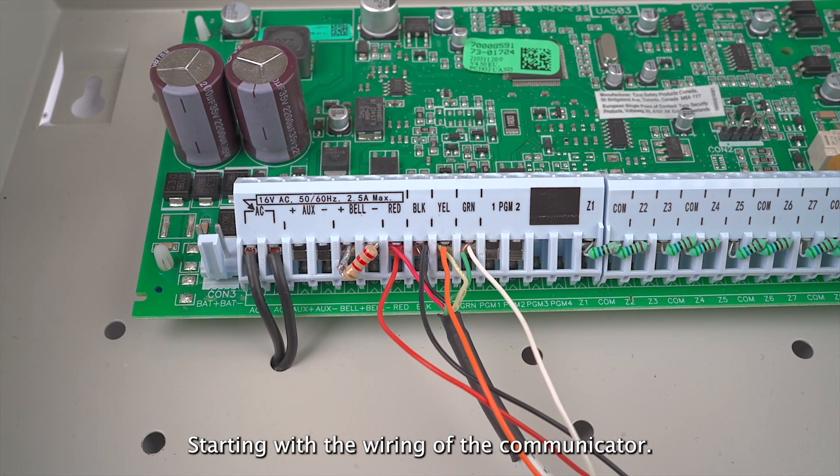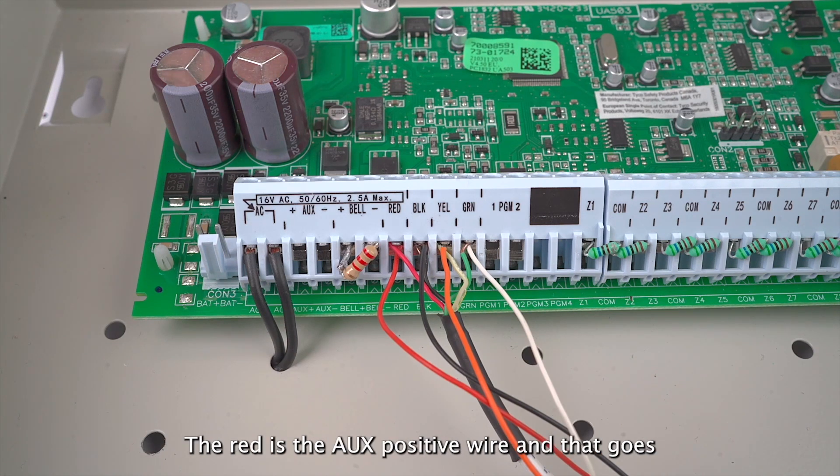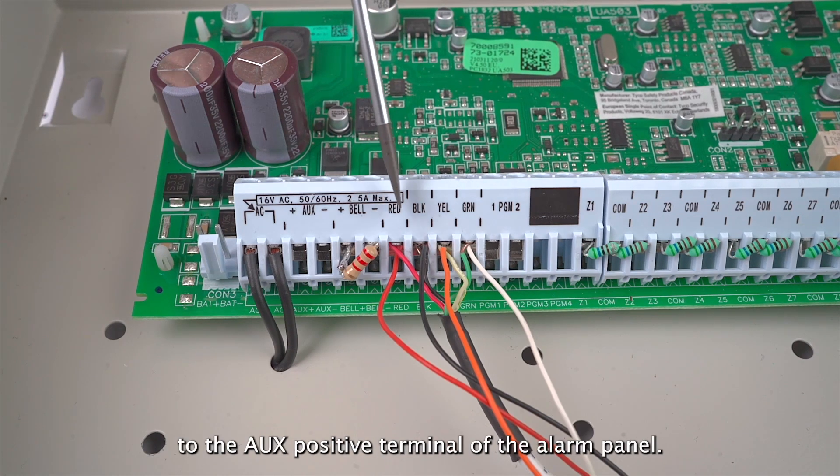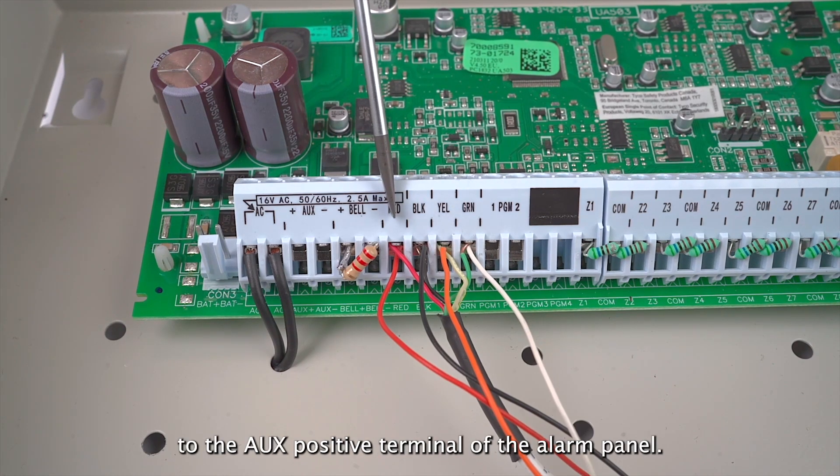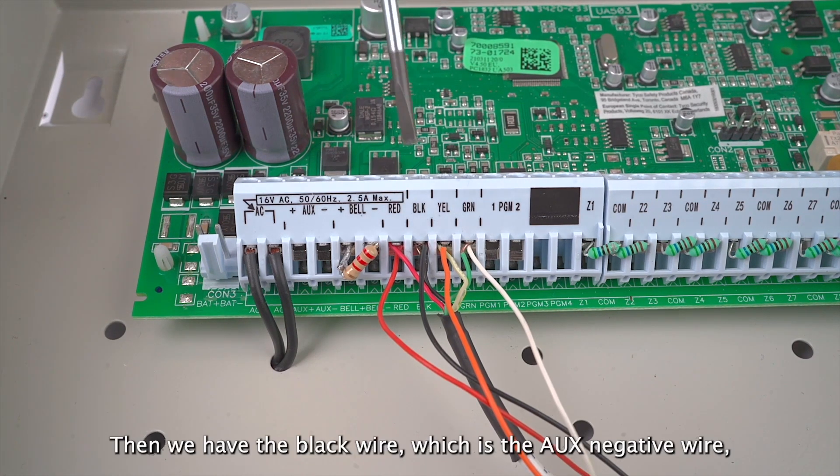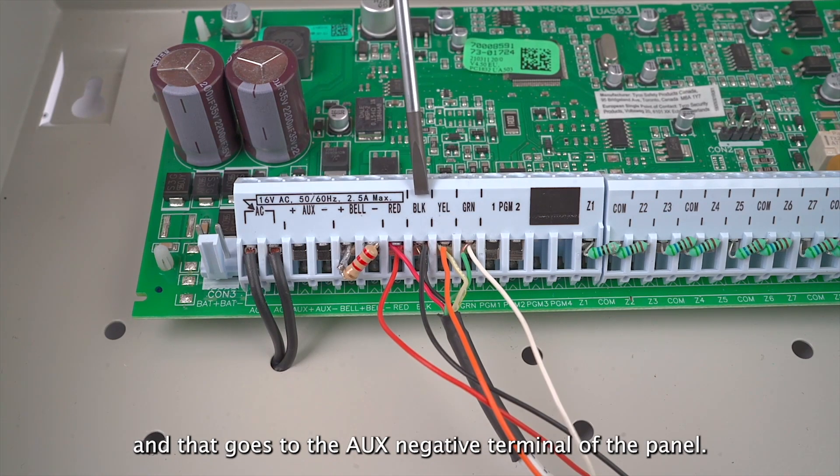Starting with the wiring of the communicator, we have the red and black wires of the radio. The red is the aux positive wire and that goes to the aux positive terminal of the alarm panel. Then we have the black wire, which is the aux negative wire, and that goes to the aux negative terminal of the panel.